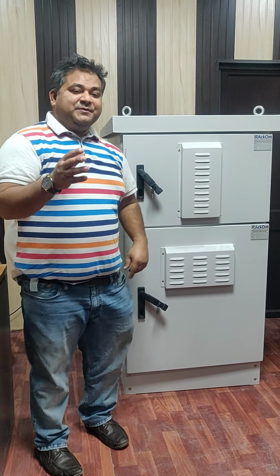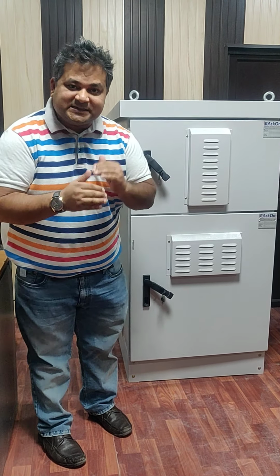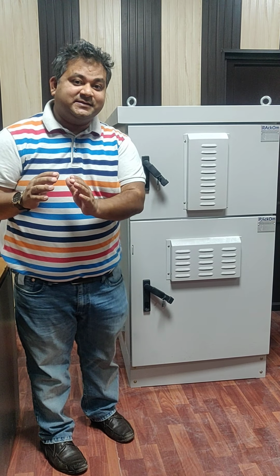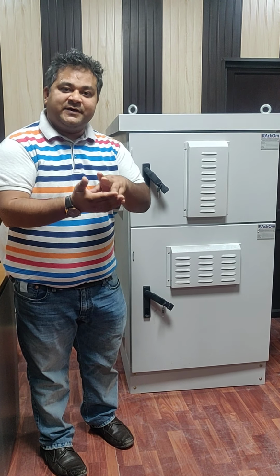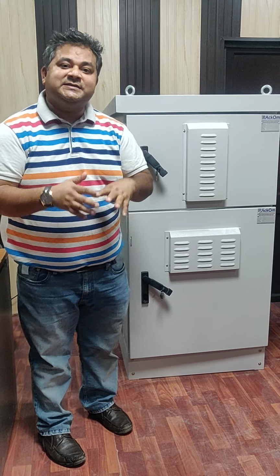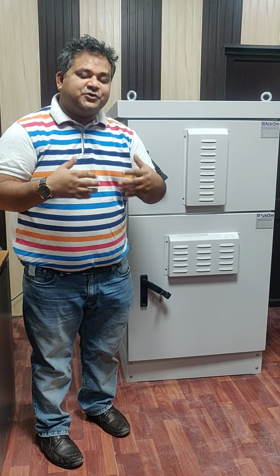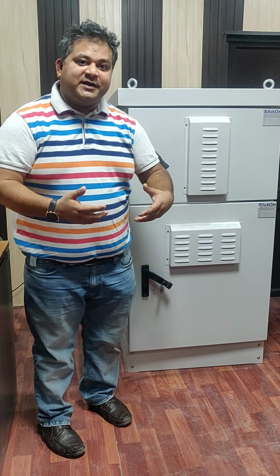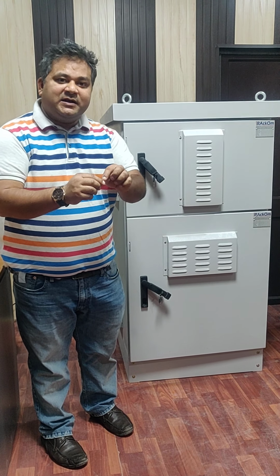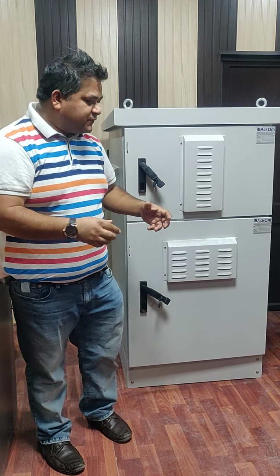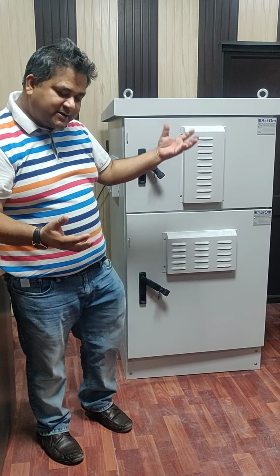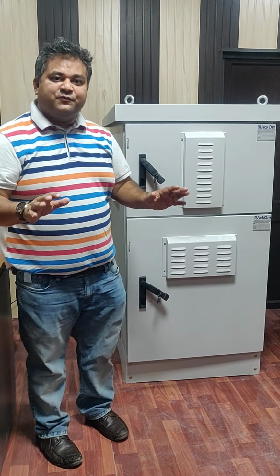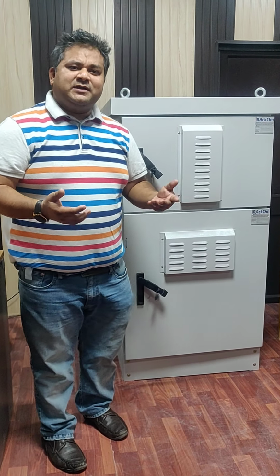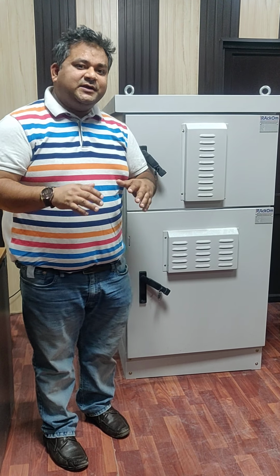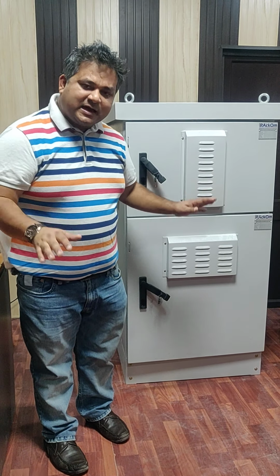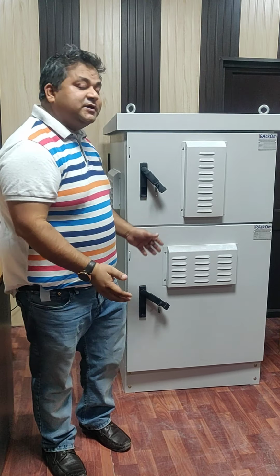So basically, IP55 allows a limited dust ingress, because we provide filters, fresh air suction, and fans for ventilation. Some dust will enter the cabinet through negative pressure or through the cable gland, sometimes because technical staff leave holes there. Once the fan sucks air through negative pressure, some dust comes in too, but it's not harmful dust - under 10 or 12 microns. So we need to clean the filters and cabinet every 3 to 6 months. That's for IP55.